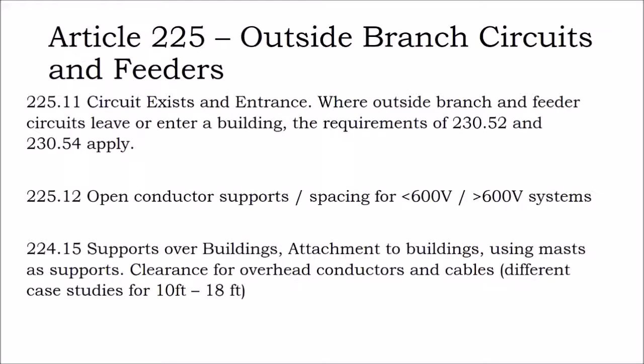Where outside branch and feeder circuits leave or enter a building, there are some restrictions that are further on down in code. Support spacings, 225.12, will govern the distance between straps, and the distance between little neoprene or rubber pad support blocks underneath your conduit as you run across a flat roof. As you go up the wall, because of the weight of the cable just hanging in the conduit, where does that weight go? Well, it goes into the conduit. And so every so often you need to strap that conduit onto the wall and transfer your load into the support wall of the building. All of these things are picked up in code.